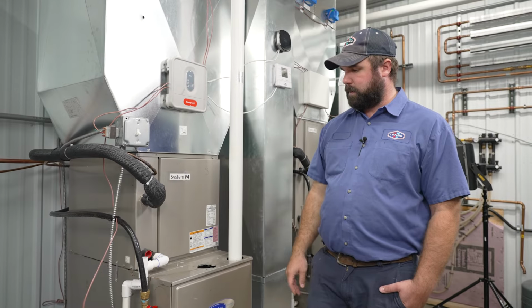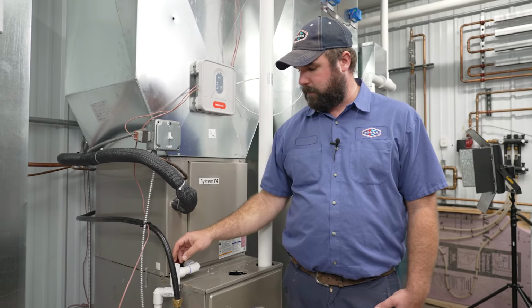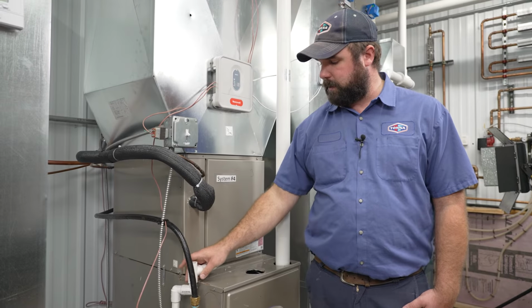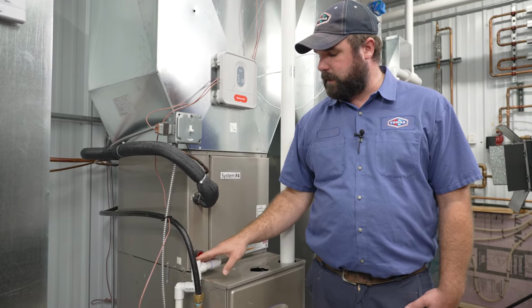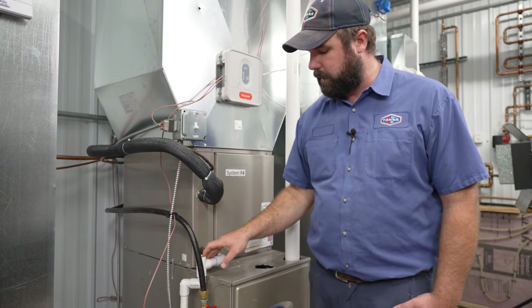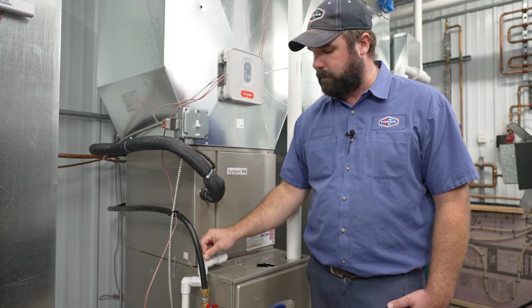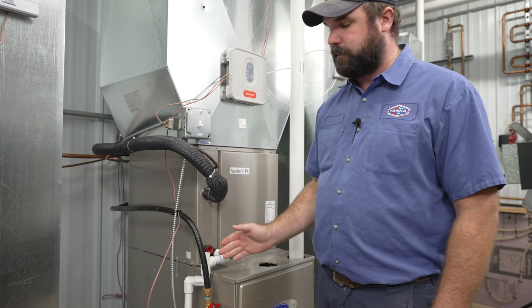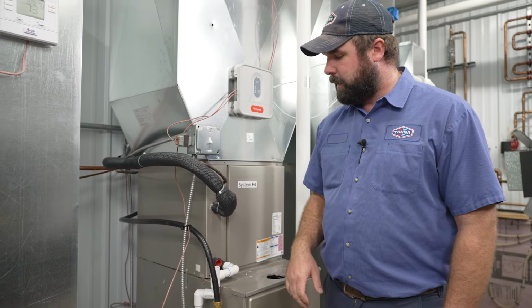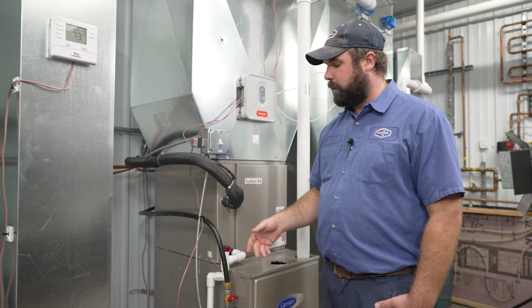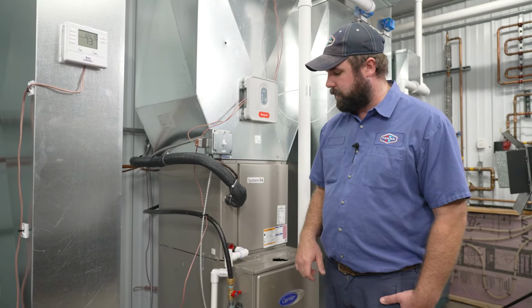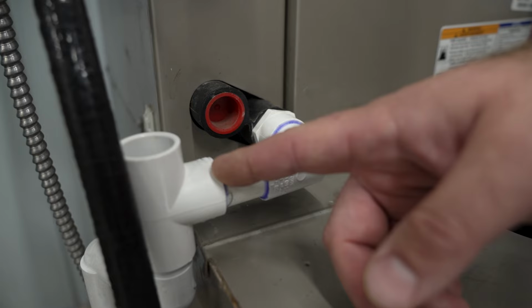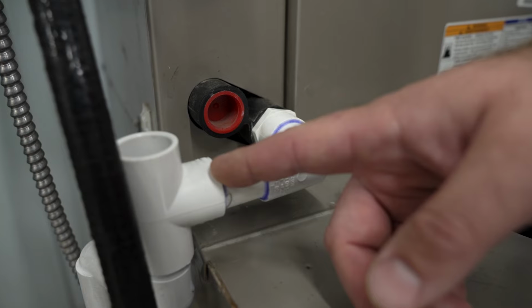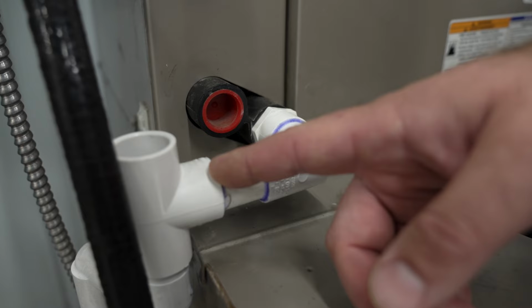We will also look down your condensate drain here. Sometimes we can see down in there, sometimes we can't. We could also pour water down here, ensuring that everything is flowing right to the drain or to your condensate pump, and that your condensate pump is working as well. So that's another vital part. That way we don't get water backing up into the furnace or leaking on your floor.